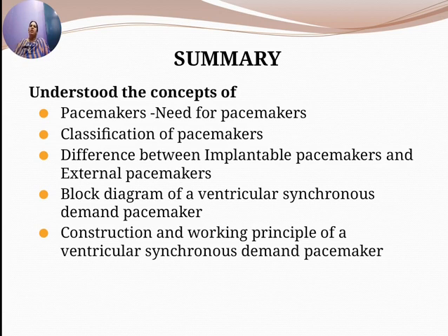The energy compensation circuit produces an increase in the pulse duration as the battery voltage decreases, to maintain constant stimulation energy to the heart. So this is the working principle of ventricular synchronous demand pacemaker or ventricular inhibited pacemaker.